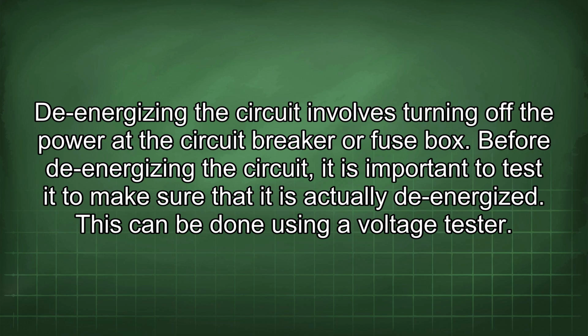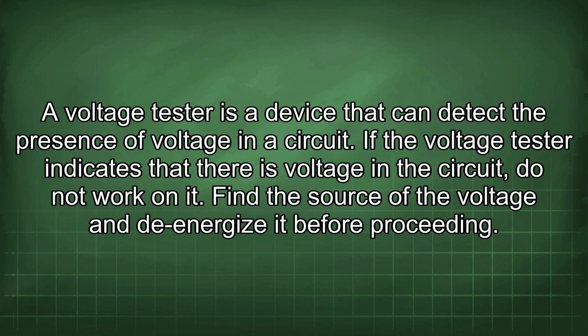De-energizing the circuit involves turning off the power at the circuit breaker or fuse box. After de-energizing the circuit, it is important to test it to make sure that it is actually de-energized. This can be done using a voltage tester. A voltage tester is a device that can detect the presence of voltage in a circuit. If the voltage tester indicates that there is voltage in the circuit, do not work on it. Find the source of the voltage and de-energize it before proceeding.